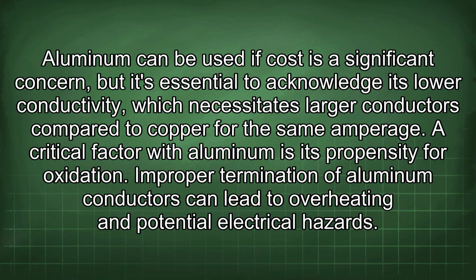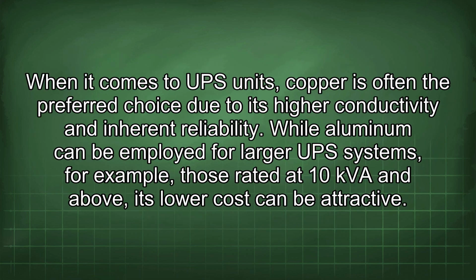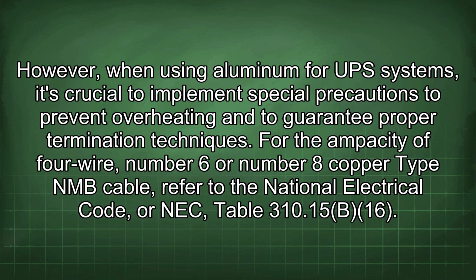A critical factor with aluminum is its propensity for oxidation. Improper termination of aluminum conductors can lead to overheating and potential electrical hazards. When it comes to UPS units, copper is often the preferred choice due to its higher conductivity and inherent reliability. While aluminum can be employed for larger UPS systems, for example, those rated at 10 kVA and above, its low cost can be attractive. However, when using aluminum for UPS systems, it's crucial to implement special precautions to prevent overheating and to guarantee proper termination techniques.